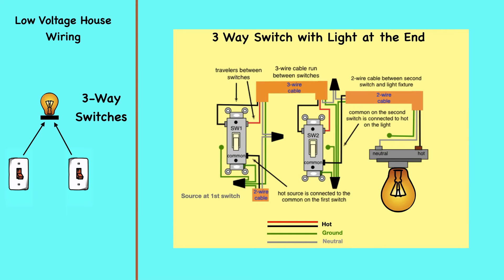In this diagram, the electrical source is at the first switch and the light is located at the end of the circuit. A three-wire cable runs between the switches, and a two-wire cable runs to the light. The black and red wires between switch number one and switch number two are connected to the traveler terminals. The hot source is connected to the common terminal on switch number one, and the common terminal on switch number two connects to the hot terminal on the light.